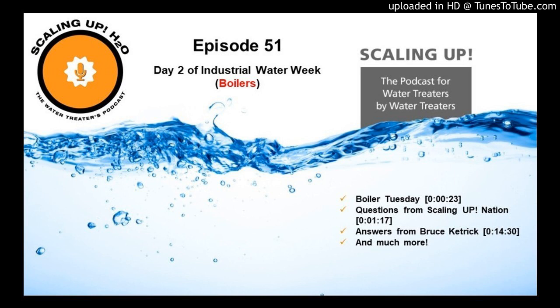Now, as that foam builds on each other, those water bubbles, as they boil, they'll pop, and they're so high, they'll pop over and get sucked out as the steam is going up through the steam header. So you'll normally see that with production equipment just simply not being able to function because there's not enough BTUs for that to work. Or maybe we can't heat something. Normally you'll see that issue because your customer's calling and saying, hey, my stuff doesn't work and I'm paying you a lot of money as my water treater. Come find out what the issue is. And by the way, I'm blaming you until you prove yourself innocent. That's just how it goes.